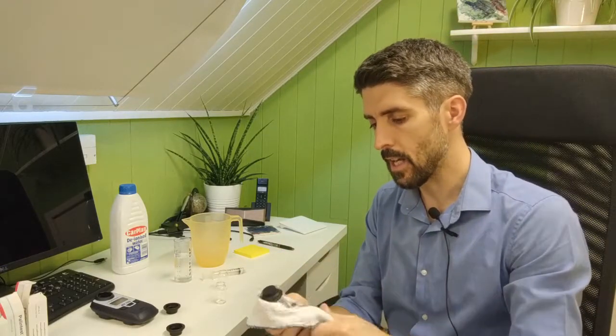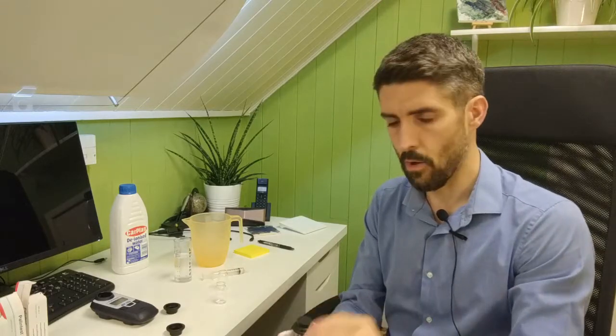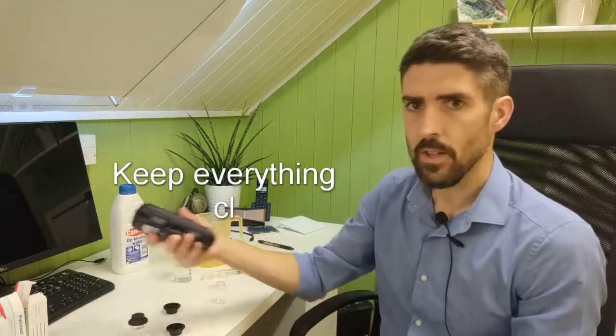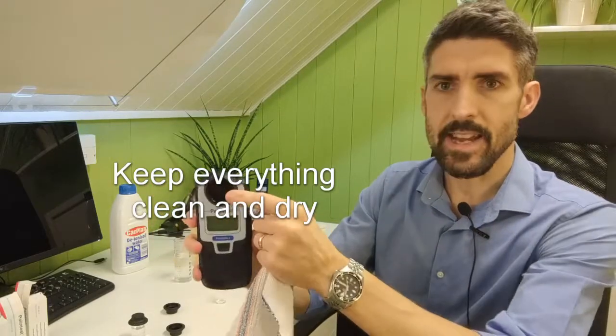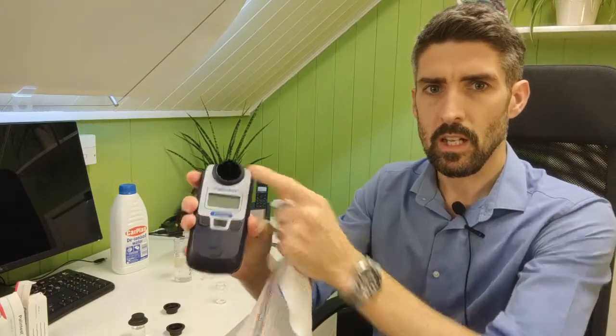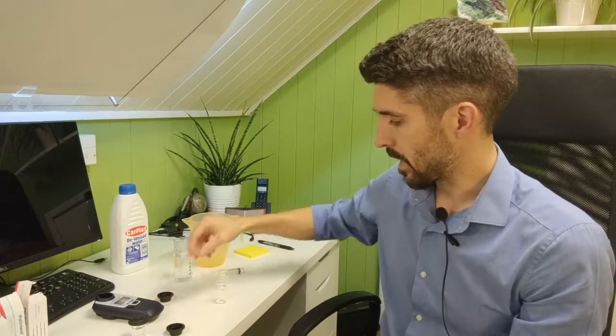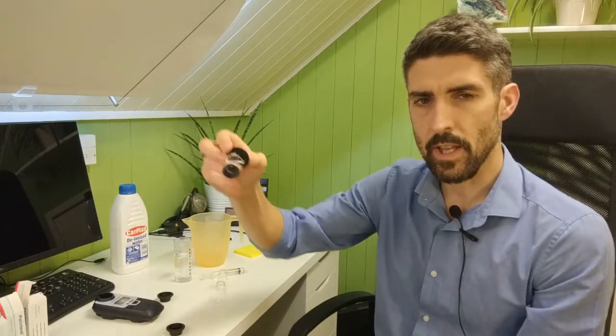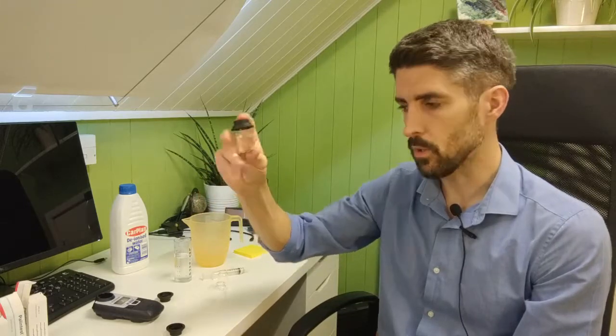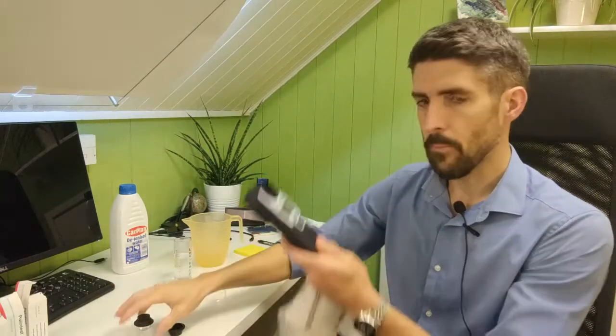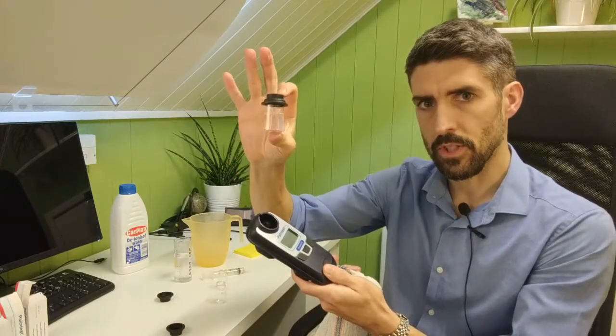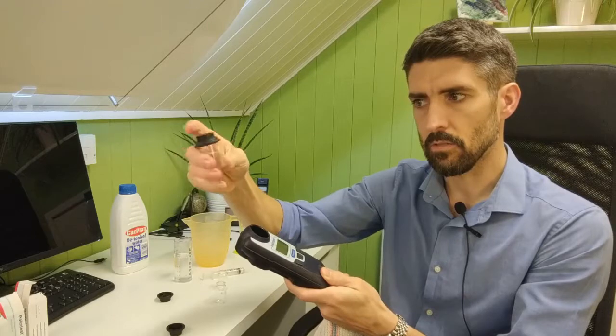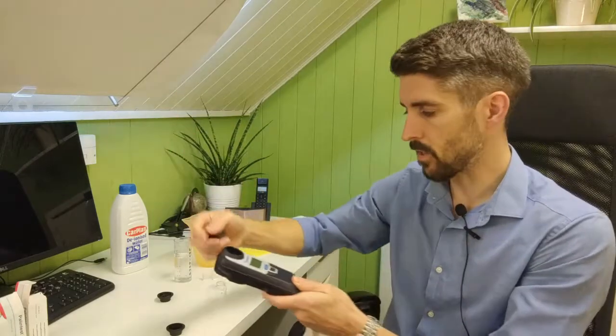And what you need to make sure you're doing on these pool tests is keeping everything clean and keeping it dry as well. Don't allow your photometer itself to get any buildup of water or grime in there over time. Keep it clean and tidy. And keep your test tubes clean and dry as well, because the way that these photometers work is this shines light through the sample, and if it's got dirt or grime or moisture on the outside of the test tube, it's going to interfere with the result.